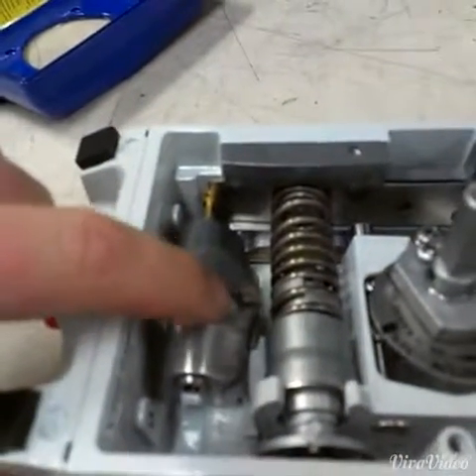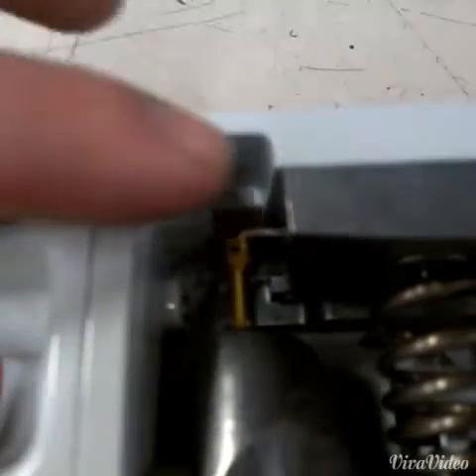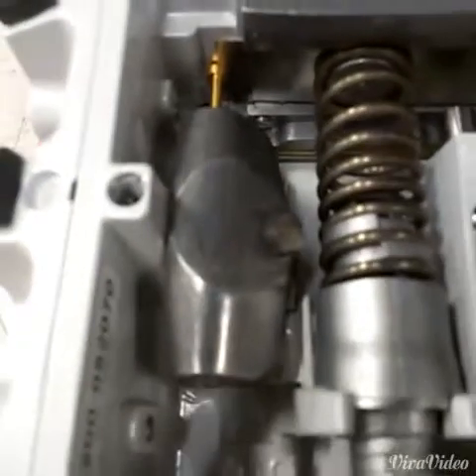What we're going to remove and inspect is the pilot valve. It's just one bolt holding it in, and then the actual rod of the pilot valve — this brass thing here — attaches onto the metal reed right here. It's just slotted, so be careful when you do that.